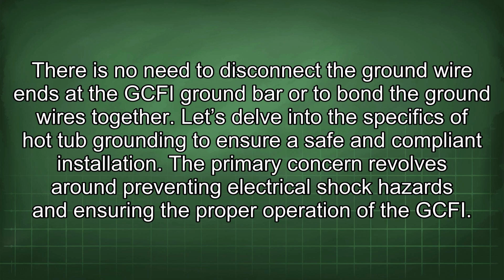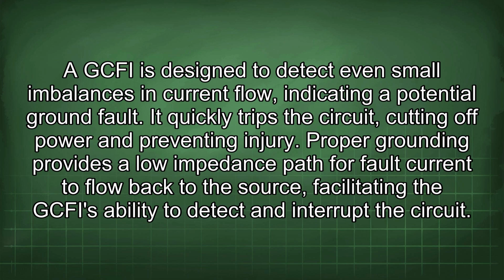The primary concern revolves around preventing electrical shock hazards and ensuring the proper operation of the GFCI. A GFCI is designed to detect even small imbalances in current flow, indicating a potential ground fault. It quickly trips the circuit, cutting off power and preventing injury. Proper grounding provides a low impedance path for fault current to flow back to the source, facilitating the GFCI's ability to detect and interrupt the circuit.